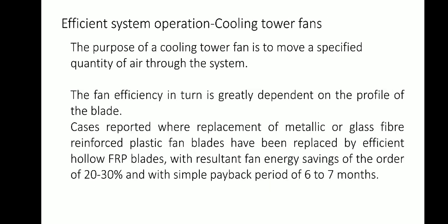Then the next parameter, cooling tower fans. The purpose of cooling tower fans is to move a specified quantity of air through the system and overcome the system resistance, which is defined as the pressure loss. The product of airflow and pressure loss is the air power developed, the work done by the fan. This may also be termed as the fan output, and input depends on the fan efficiency. The fan efficiency in turn greatly depends on the profile of the blades.